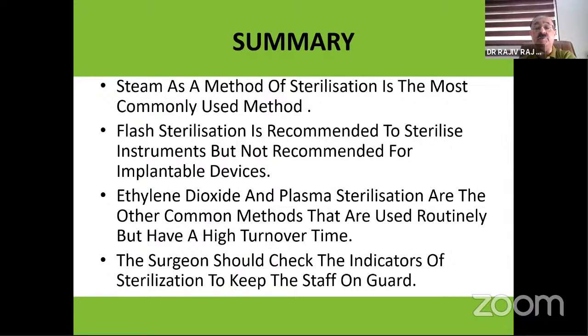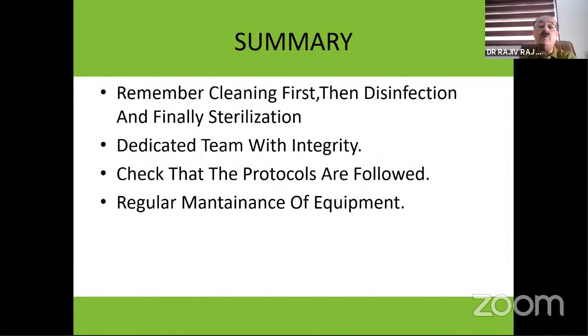The surgeon should keep a check of the indicators and keep the staff on guard. Remember, cleaning is very important. The best of sterilizers is not going to give you 100% result if disinfection is not done thoroughly. You need a dedicated team with integrity. I think this is a team that does not run into the theater to assist at the time of surgery, gets up in the morning at 3, runs a Bowie-Dick test, because if they are tired, then they try to cut corners. Check that all the protocols are followed, and regular maintenance of equipment is very vital.